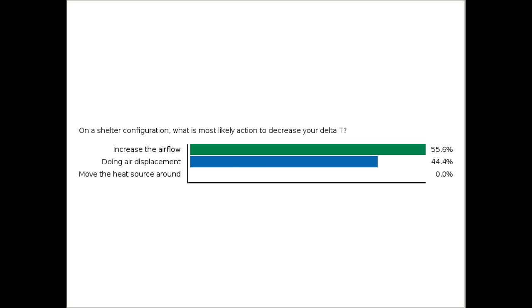Right, we've had 9 participants and very mixed returns, but essentially it's increasing the airflow, because there's a direct relation between the airflow and the delta T that the system will be able to achieve. Moving the heat source around will definitely drop the restrictions on the site. And doing air displacement, as we know, will also favor the destratification of the air and get rid of hotspots on the site. But the most important thing to decrease the delta T overall on the site is to increase the airflow. And that's what we're trying to achieve with our system.